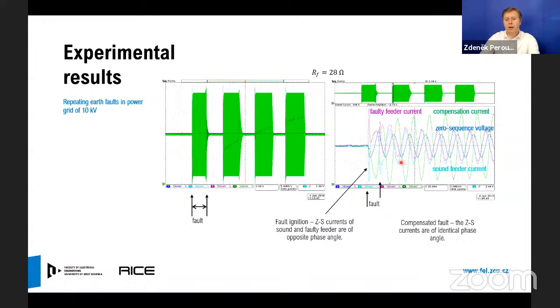Just to illustrate how fast our compensation can be, here you see the generation of the compensation current. Here you see the current of the faulty feeder. Here you see the current of the sound feeder, and the fault is compensated when the currents have identical phase angle, which you can see occurs very fast. So we are able to compensate the ground fault in below 20 milliseconds.